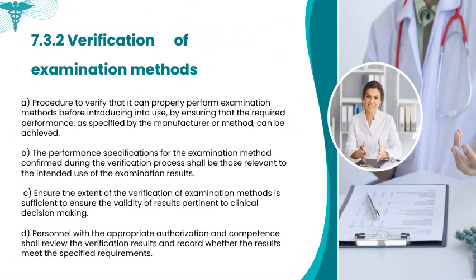The laboratory must have a procedure in place to verify any examination method before it is put into use. This verification ensures that the method performs as expected and meets the performance claims made by the manufacturer or described in the method itself. The performance characteristics confirmed during verification must be directly relevant to how the test results will be used in clinical practice.